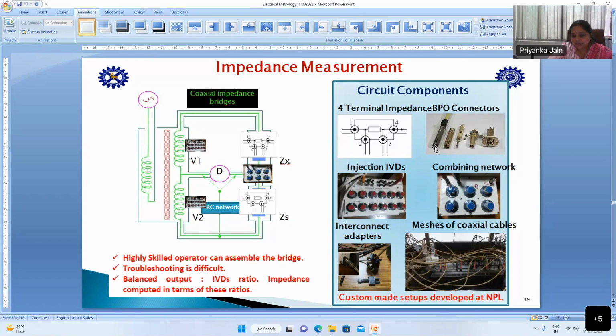These are the interconnects. You can see the coaxial cables and BPO connectors. All coaxial cables are here. We give measurements through coaxial cable to minimize the effect of induced EMF. If you flow current through this conductor, the inner conductor carries the current in the forward direction, and the outer conductor returns the current back to the supply. So the net EMF induced by the forward current in the circuit is compensated by the reverse current to the supply, so that you can get interference-free measurement with these coaxial connections. So coaxial connections, all four terminals, and inductive voltage dividers come into the picture.